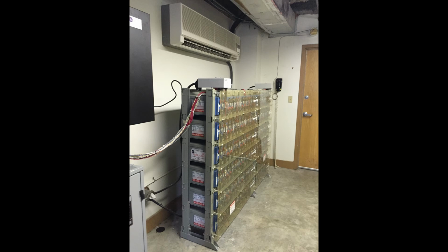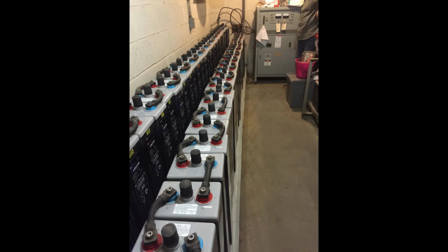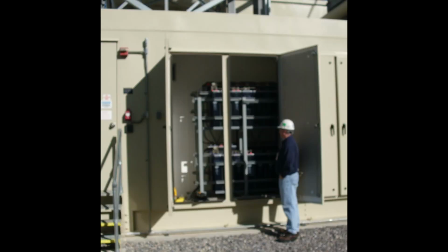If you have located the cell that has the path to ground, but you cannot see any evidence of the path, the next step is to verify that the cell is structurally intact. This requires performing a pressure check on that cell. We usually use 3 to 10 psi, as that has worked for us to find most of the leakers. That procedure is explained in Tech Tip 25, pressure checking VRLA cells.